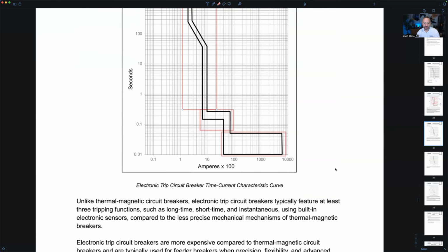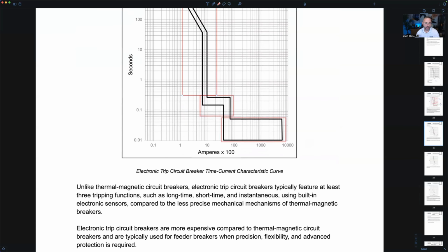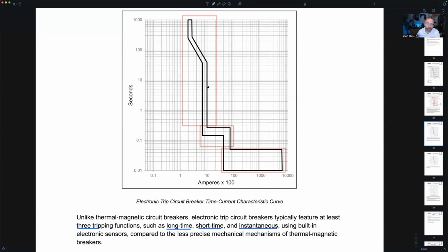So electronic trip circuit breakers, all the times, these are the ones that are much more adjustable. And look, yeah, it has at least, a lot of times they can have more, but at least three tripping functions. So the ones we just drew was the instantaneous on the bottom, right? And the short time, and then the long time. Long time is always your overload, but maybe I want more flexibility in my protection settings so that, hey, I don't just want to trip all the way out here, right? From here all the way to about what? 200 seconds, right? Maybe I want a little bit of tripping here in this region. I want to be a little more selective.